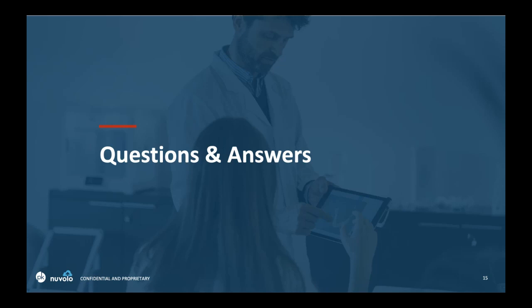Absolutely. So we do have an integration with PartSource. What's very nice about it is you'll literally go from a work order directly into PartSource and really the catalog experience that you've come to love over time. And there's a reason why PartSource is largely the biggest parts supplier within the healthcare technology management space. We wanted to be able to keep that user experience. And so upon completion of that work order, the information would then be passed back into Nuvolo to go through the receiving process and actually get the itemized cost associated with the work order. So we have a very strong PartSource integration. Thanks, Dustin.